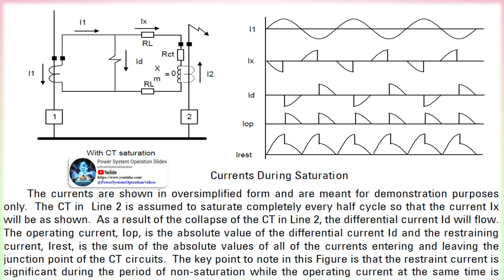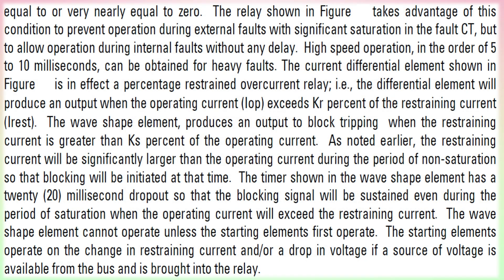A percentage restrained differential relay takes cognizance of the fact that there may be error current in the differential circuit. The relay will operate when the differential current ID is greater than some percentage of the total restraint current. The amount of restraint is generally adjustable. The characteristic of the relay is such that as the restraint becomes larger, so does the operate or difference current required to produce an output, producing the characteristic slope dependent on the percentage restraint setting.